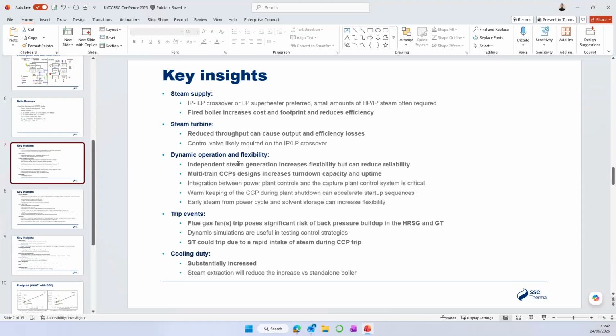On dynamic operation and flexibility, if we're looking at the independent steam generation case, so a fired boiler or a CHP, it does increase your flexibility because you can start that system up before your power plant does, say, and generate steam early. But it's also a notable source of reliability issues. So it's another point of failure in the system that can affect the reliability of your plant if that goes down while you want to operate your CCP. You don't have any steam.